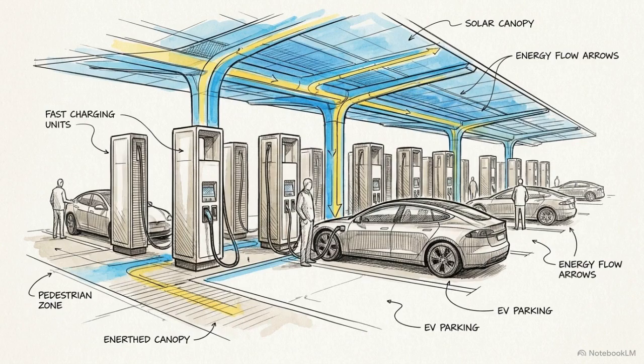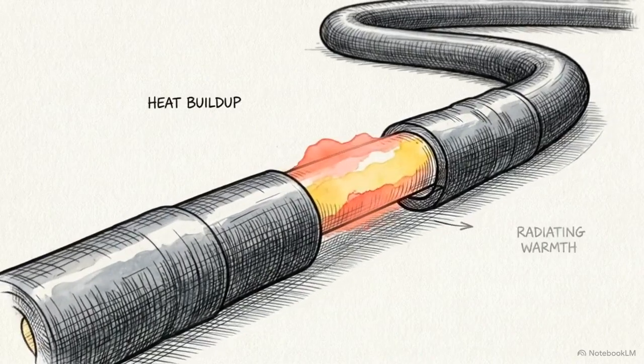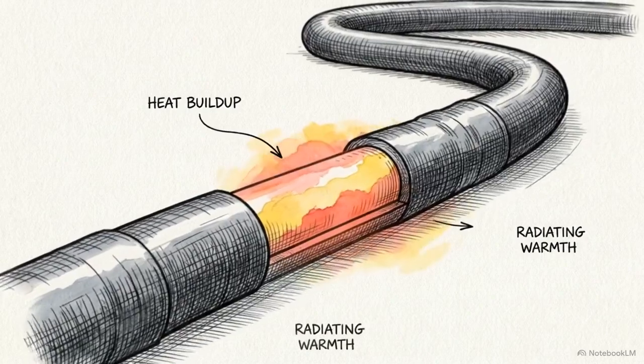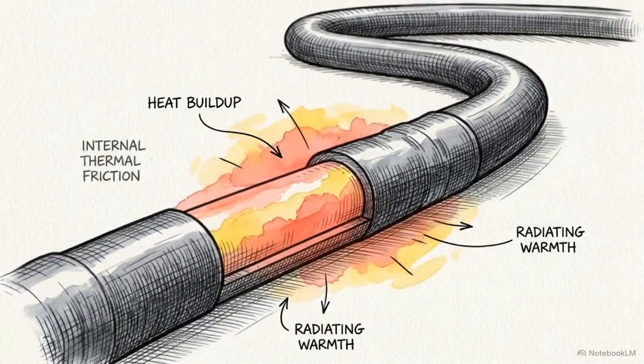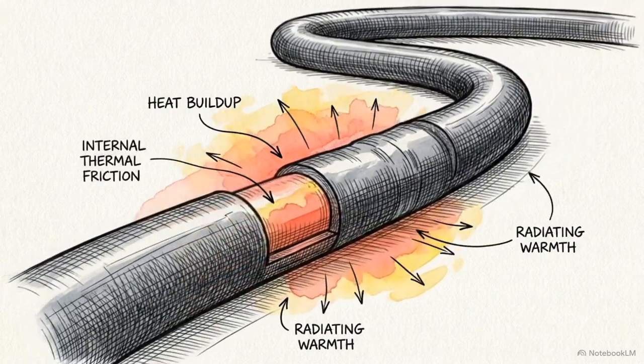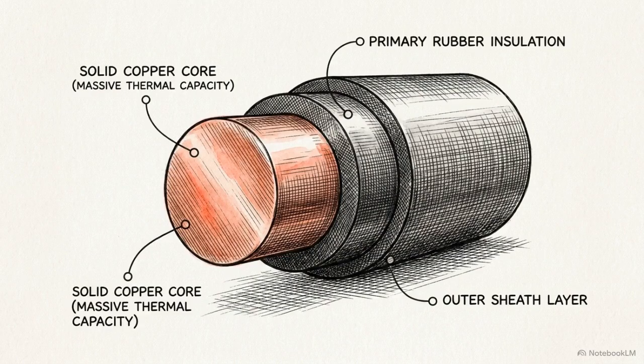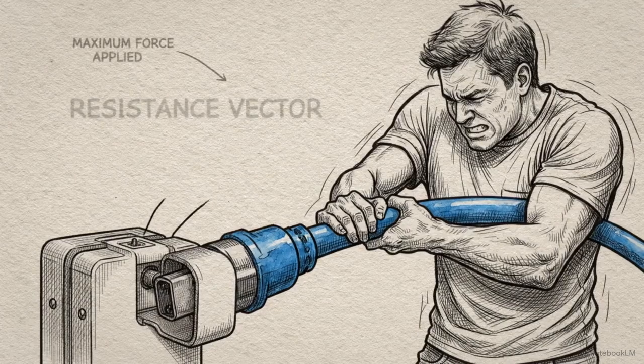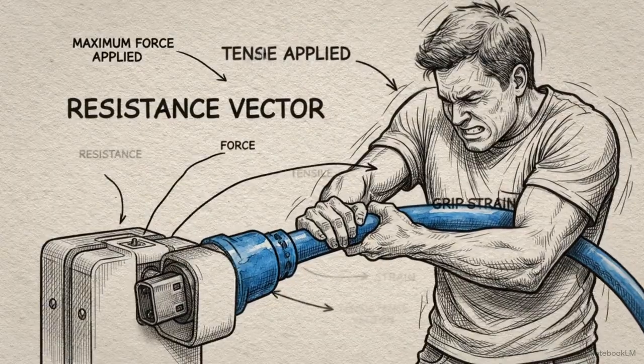Relocating the heavy physical hardware into a stationary cabinet is the only way the physics of a 30-minute highway pit stop actually works. Pumping hundreds of amps of raw current straight from a cabinet into a car creates massive thermal friction inside the physical cable. If you relied on standard copper wiring to absorb that heat, the charging cable would have to be so thick and heavy that a person couldn't comfortably lift it off the stand.